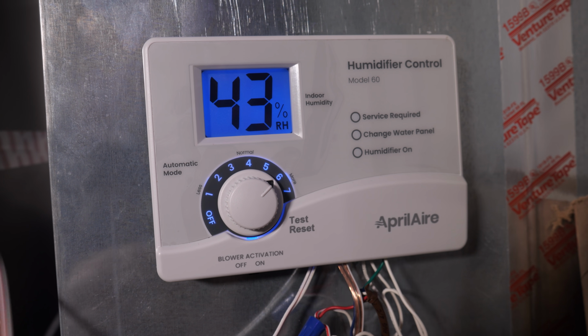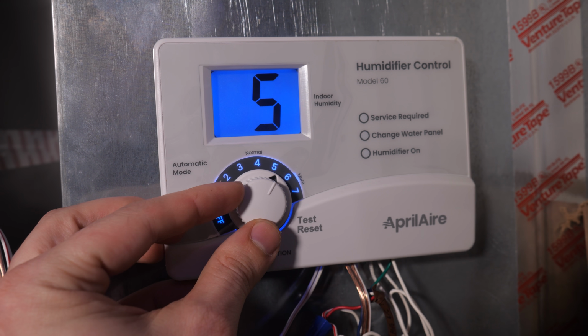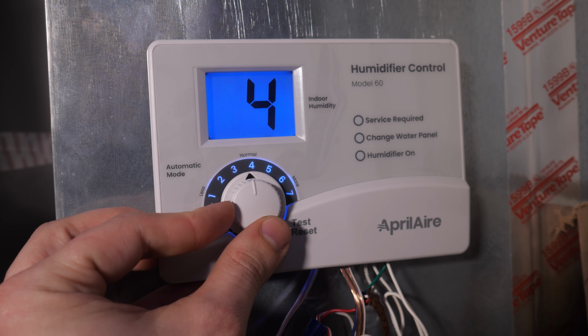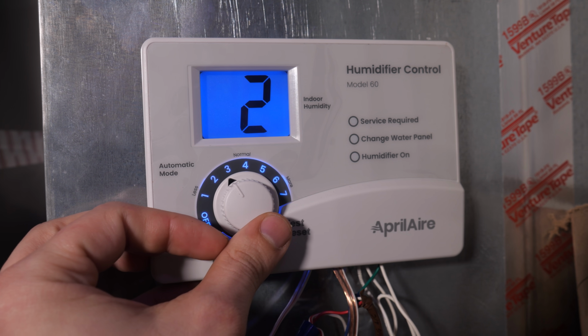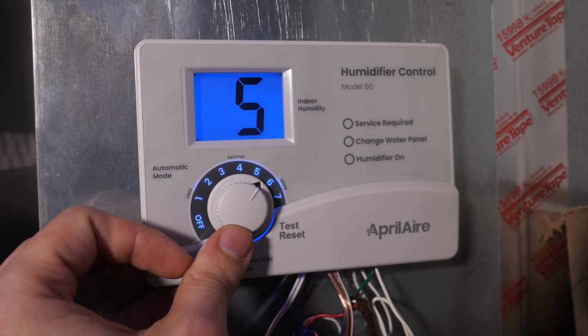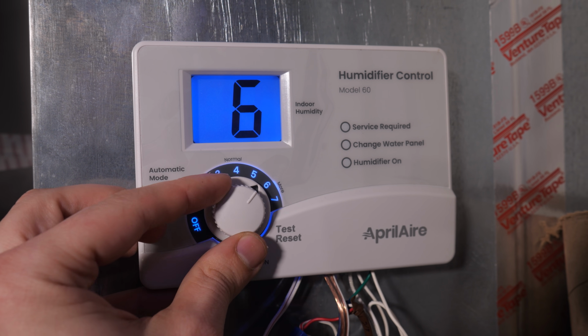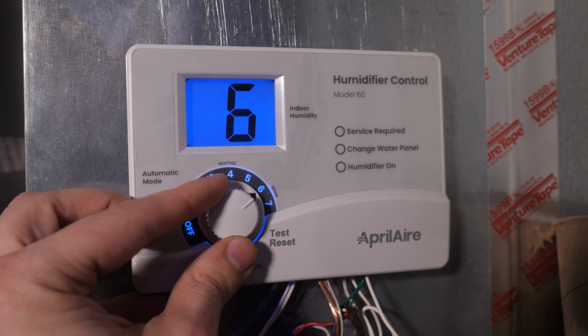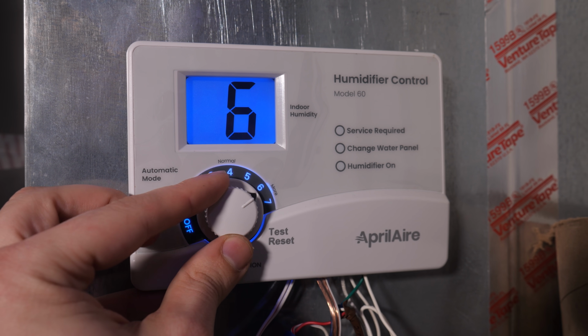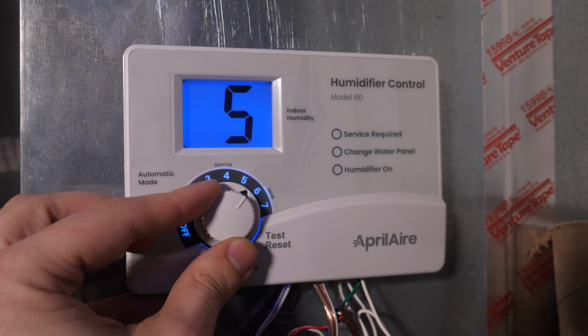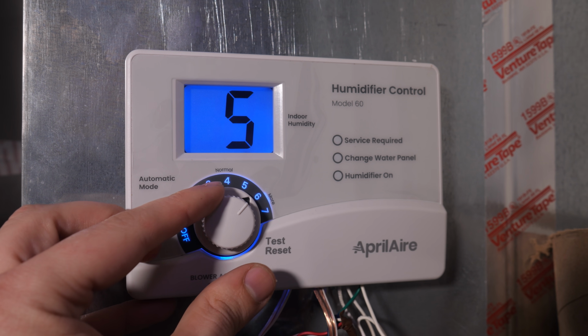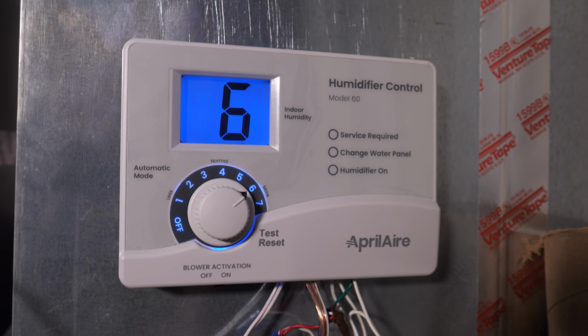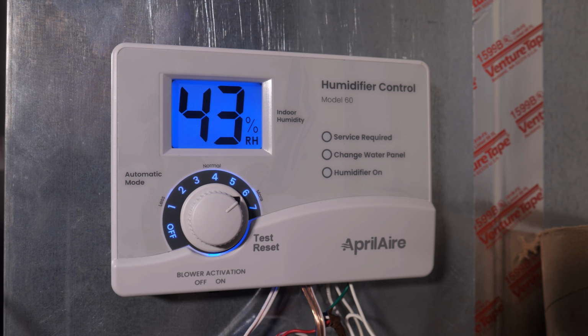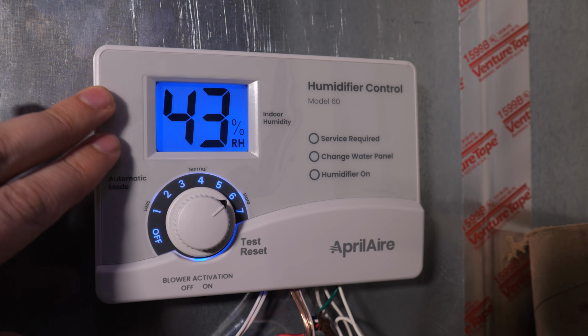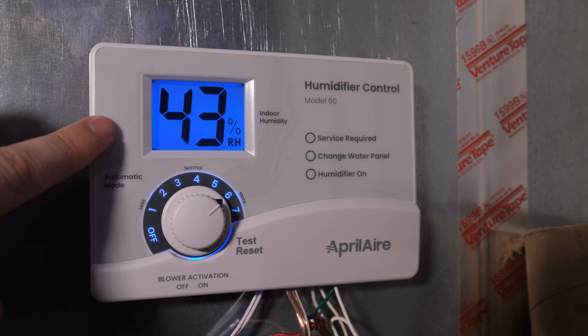The other thing I don't like about this? It won't tell me what it thinks the outdoor temperature is. It should throw an error code if the sensor goes bad, but what if the sensor is simply drifting over time? I'm not going to know that unless the drift is bad enough to cause it to over or under humidify. Since I've installed this, the outdoor temperature hasn't fallen much below freezing, so I'm not even sure yet that it's working as intended. That's cool since, that's the whole reason I did this.